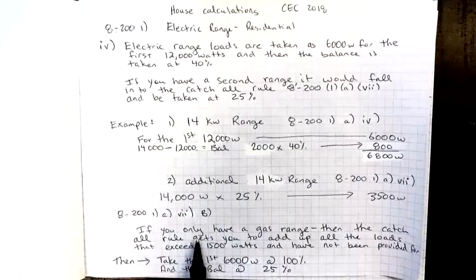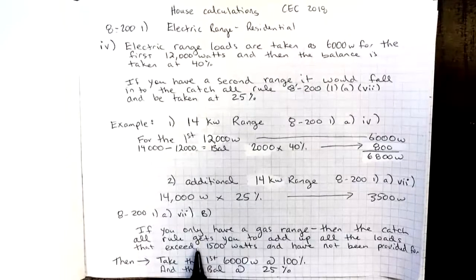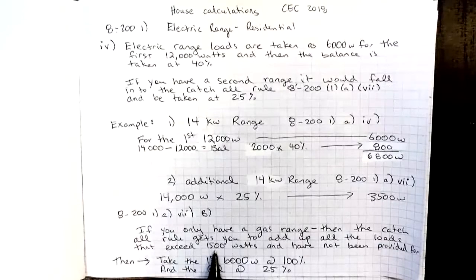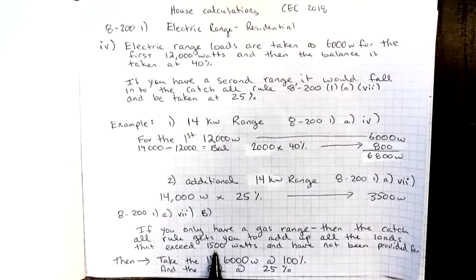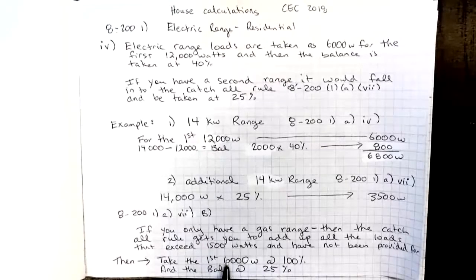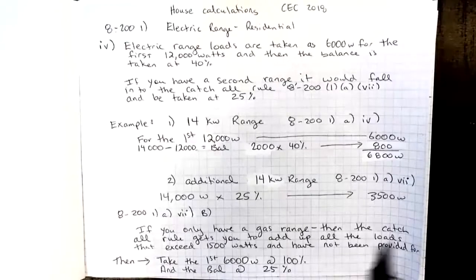If you only had a gas range, then the catch-all rule gets you to add up all the loads that exceed 1,500 watts, and that have not yet been provided for. They will take the first 6,000 watts at 100%, and the balance at 25%. And I'll show you an example of that when we get to the catch-all rule.